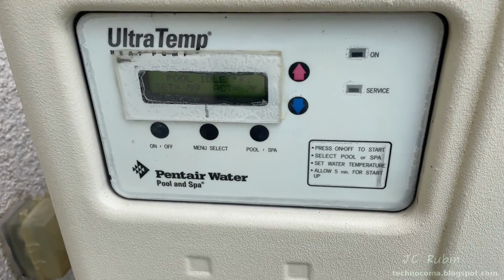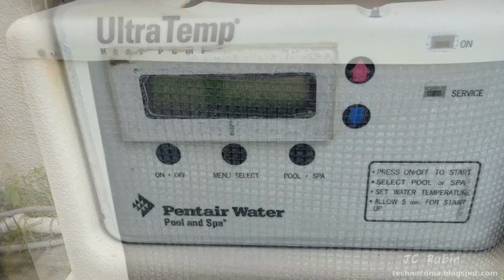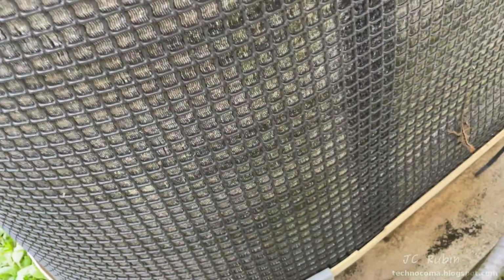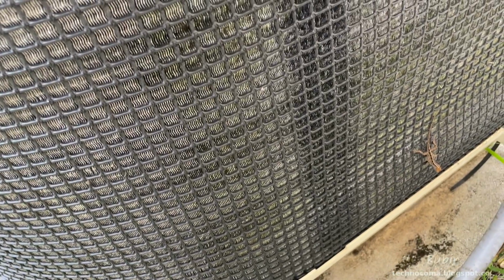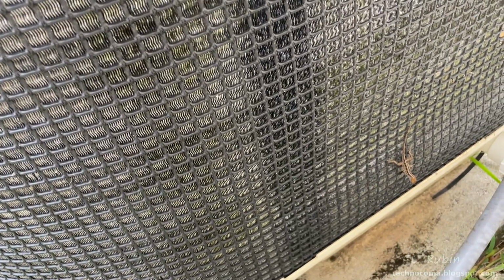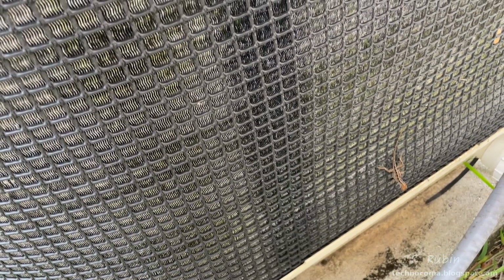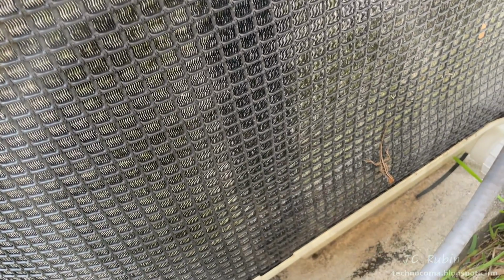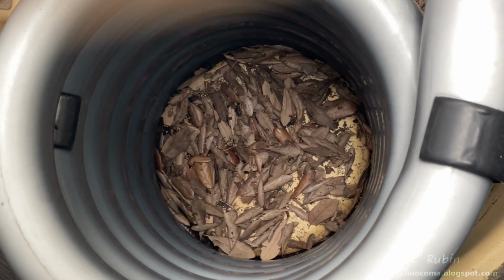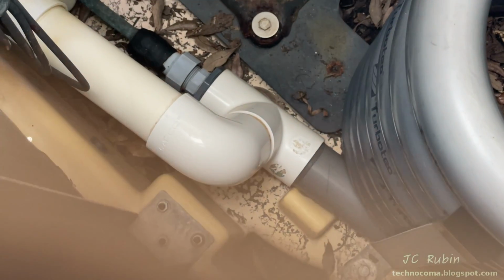Electronically, everything seems to be in working order. While this outer layer has done well to protect the coils from bending and damage, there is a lot of dirt caught in these coils. We could see a lot of green as well on the lower portion of the coil. There must be water filling up inside, no surprise given the amount of detritus that has collected in this unit. We could also see that it has caused rusting on a lot of the metal surfaces, especially the horizontal ones.